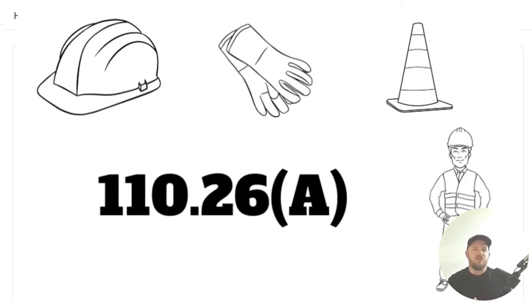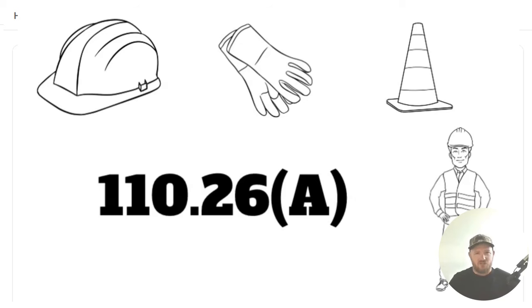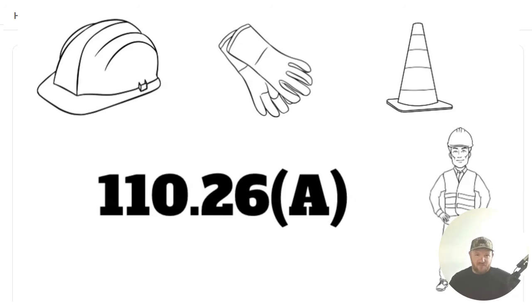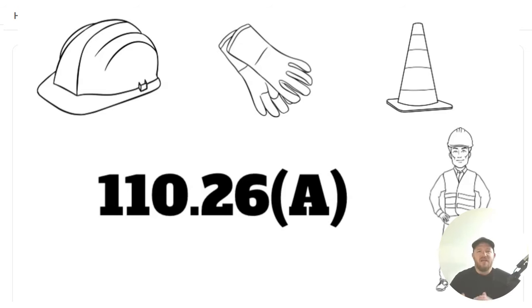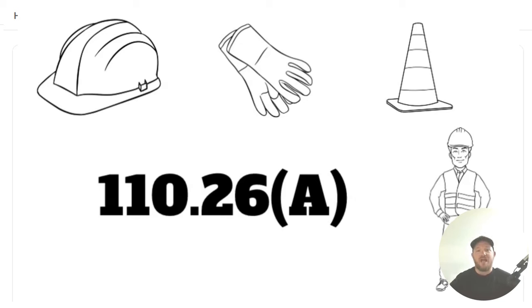It's a big misnomer that only electrical equipment that is going to be worked on while energized is required to have the working space. And that's partly true. If it's required or if it's likely to be worked on while energized, it's required to have the working space dictated in 110.26A.